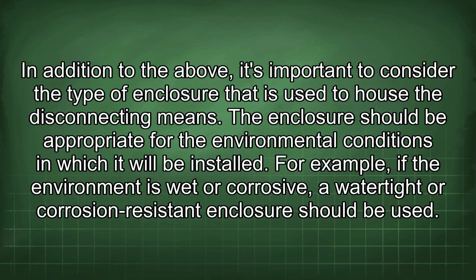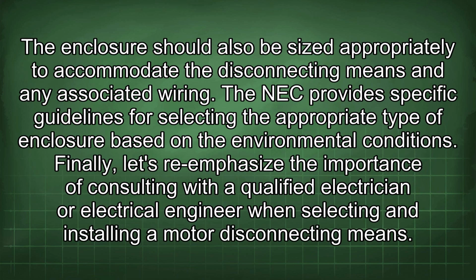In addition to the above, it's important to consider the type of enclosure that is used to house the disconnecting means. The enclosure should be appropriate for the environmental conditions in which it will be installed. For example, if the environment is wet or corrosive, a watertight or corrosion-resistant enclosure should be used. The enclosure should also be sized appropriately to accommodate the disconnecting means and any associated wiring. The NEC provides specific guidelines for selecting the appropriate type of enclosure based on the environmental conditions.